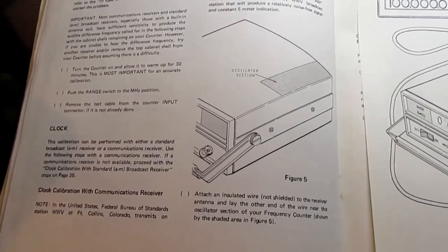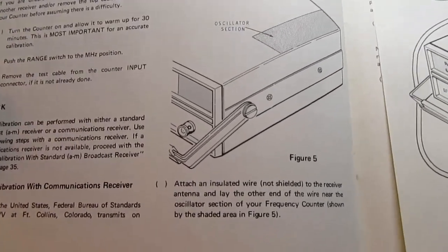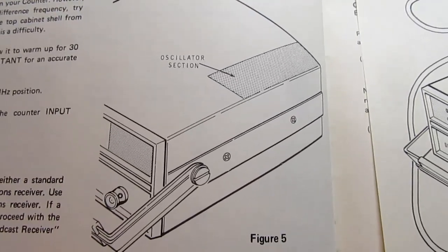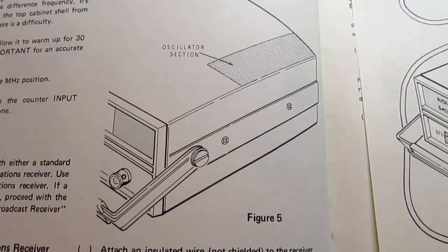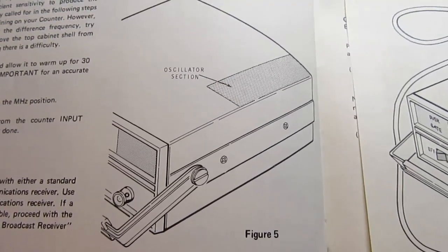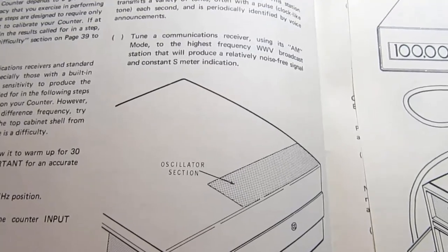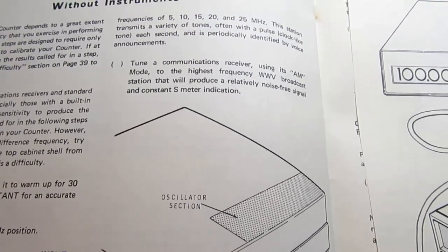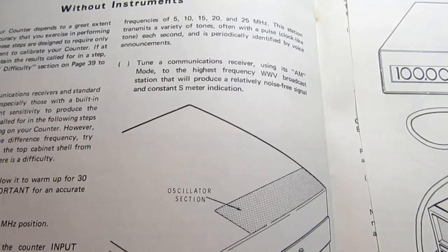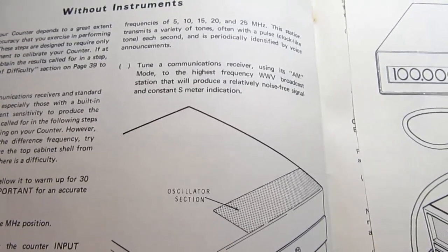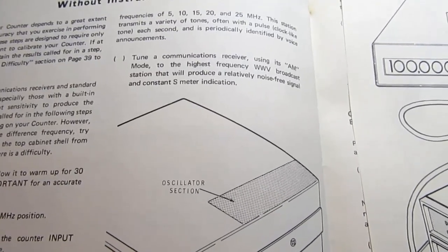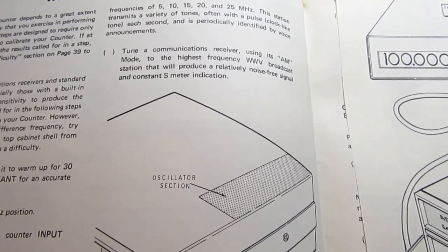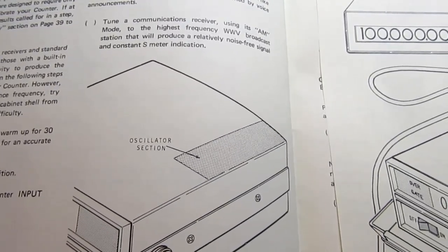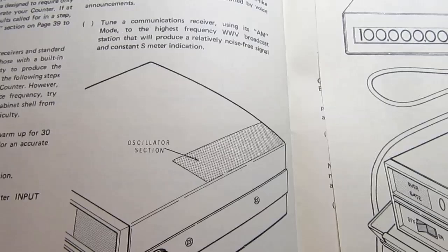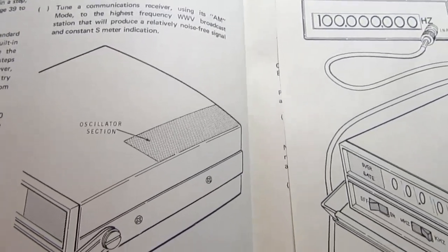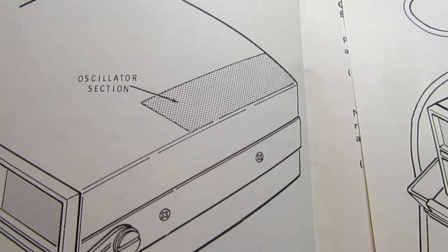The calibration without instruments involves using the oscillator section or the clock section of the frequency counter, which should be oscillating at 1 megahertz, and then tuning a communications receiver to one of the Federal Bureau of Standards stations in Colorado, which transmits frequencies of 5, 10, 15, 20, and 25 megahertz. And you wrap a piece of wire around the antenna of the communication receiver and lay it over the case near the oscillator section.